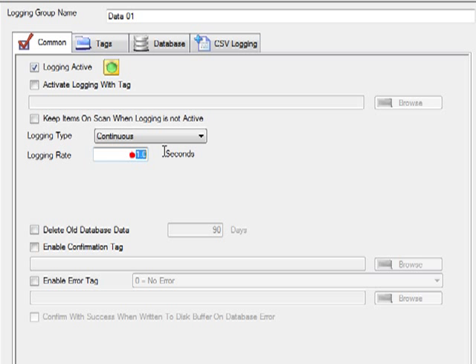Let's use the continuous type, and we can specify the logging rate. The logging rate can be sub-millisecond, with the resolution of OPC Database.NET at 100 nanoseconds. If you're logging at a slower rate, say once an hour or once a day, the logging will occur either right at the top of the hour or right at the top of the day as well. So it's evenly divisible at whatever time frame you select.